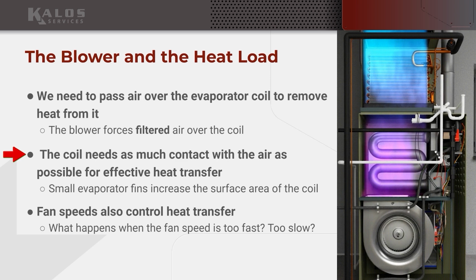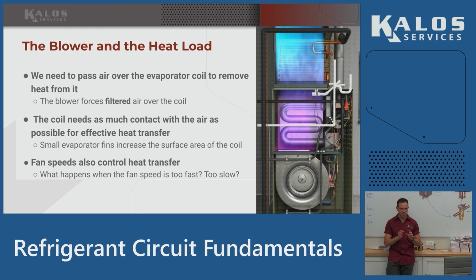But the more surface area I can put in contact with the air, the better the heat transfer I'm gonna have, right? So that's why the manufacturer will put a bunch of little fins all over the thing. They're trying to create more surface area in contact with the air to get better heat transfer across the coil. The fins are also created, if you look at them really closely, you notice they're going like this. Those thin metal fins are not perfectly straight. That way, when the air is moving through, the air is forced to smash into each side.